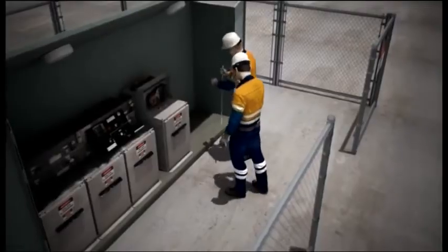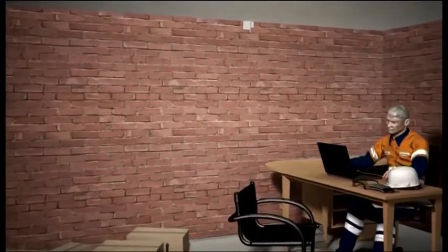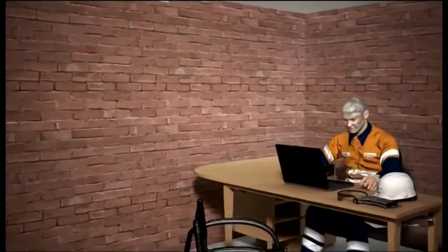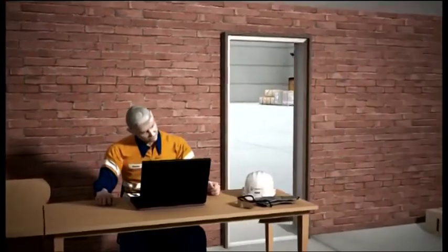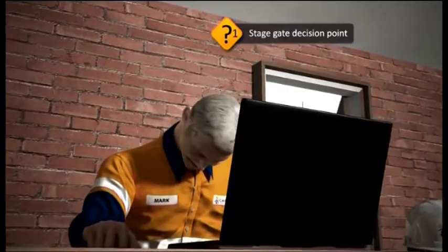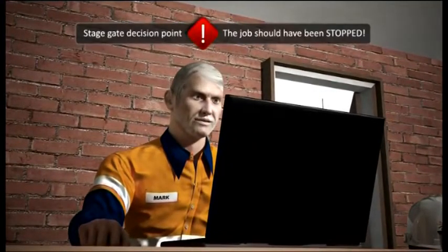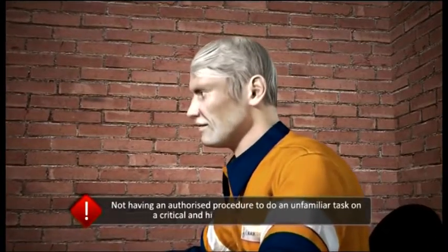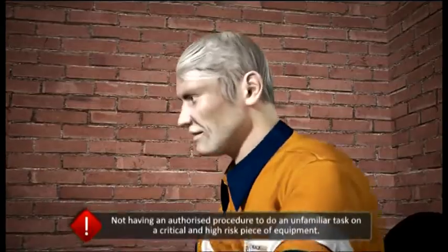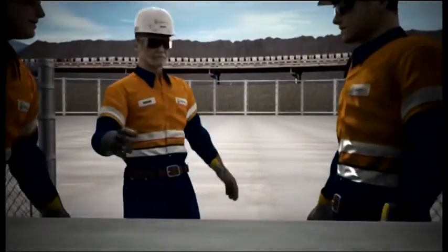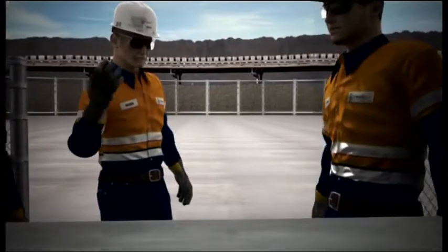Being unable to find the necessary information in a manual or online, or to contact the original equipment manufacturer, no one was able to adequately identify and control the hazards associated with replacing the switching mechanism. This is clearly a stage gate decision point, the first point where the job should have been stopped. Not having an authorized procedure to do an unfamiliar task on a critical and high-risk piece of equipment. The workings of the switching mechanism are a complex and unfamiliar task.